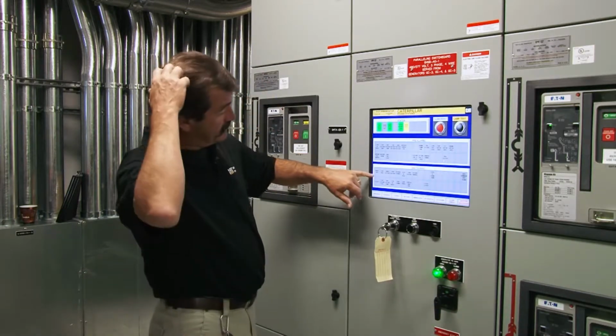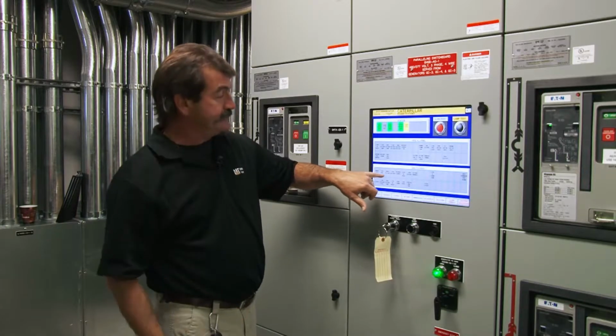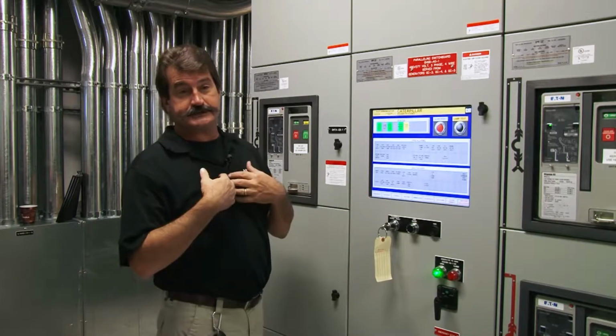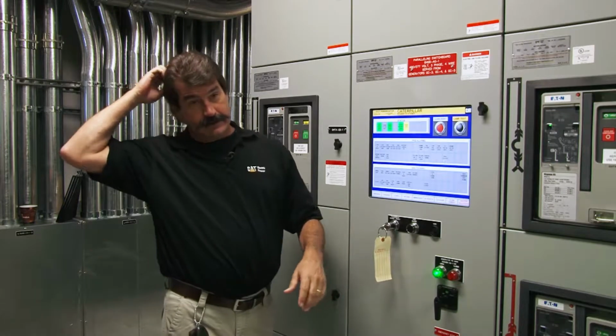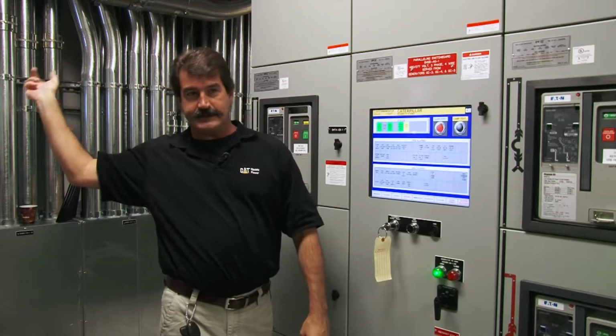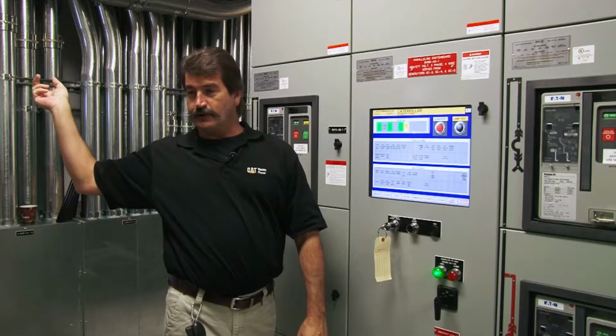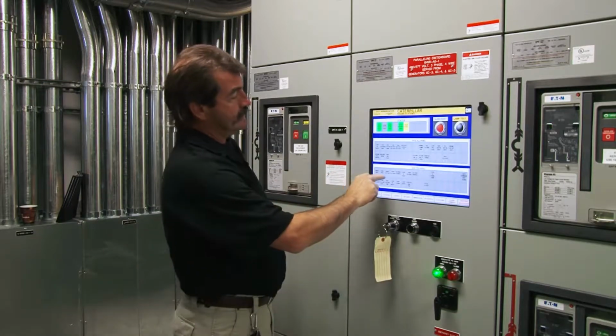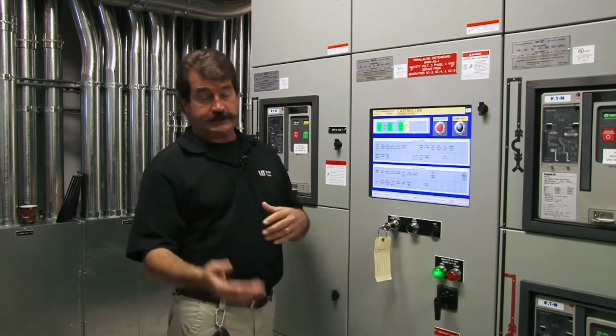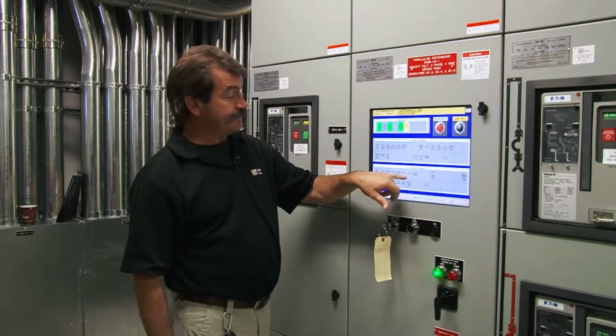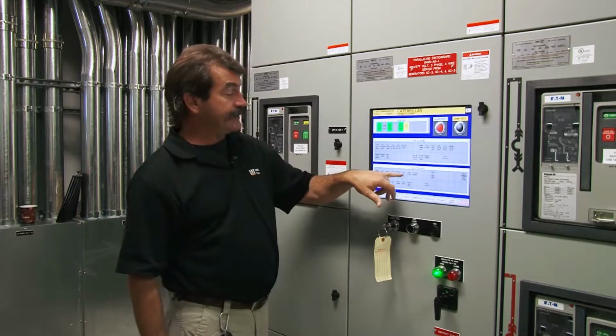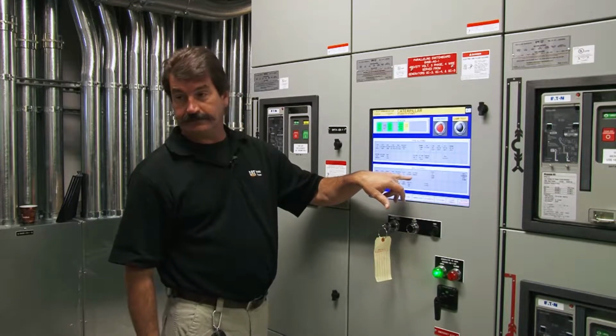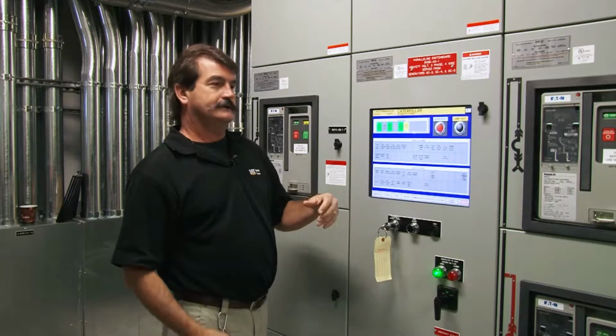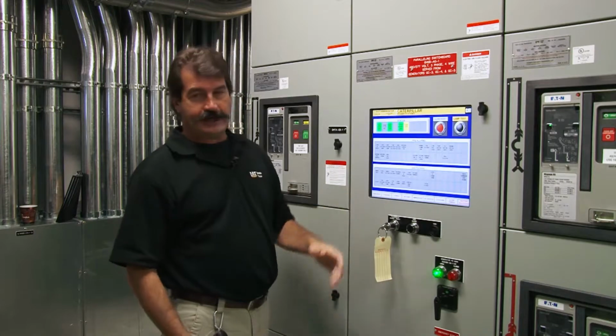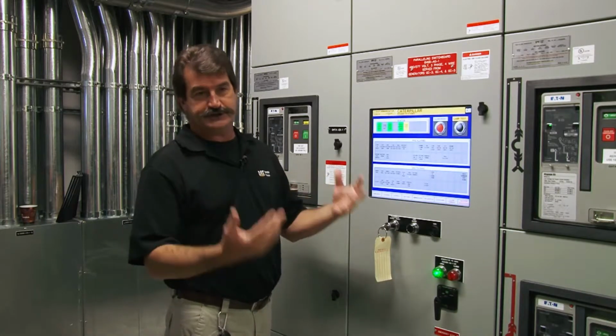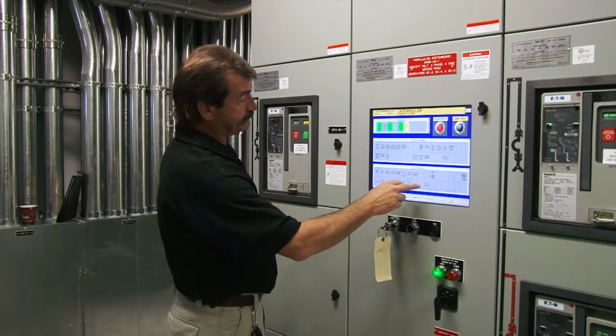Okay, pre-alarm shutdowns, over and under frequency, over and under voltage. This is us doing this, not the EMCP out there that has that. They have their own under and over for these things. Reverse power, same, and loss of field, overexcitation. All this right here is us doing that. So if you lose it that way, we shut it down for our reasons.